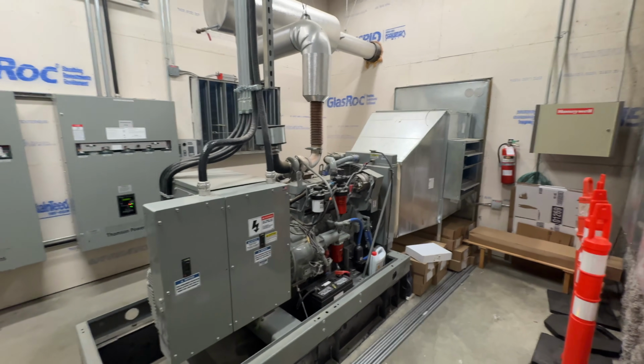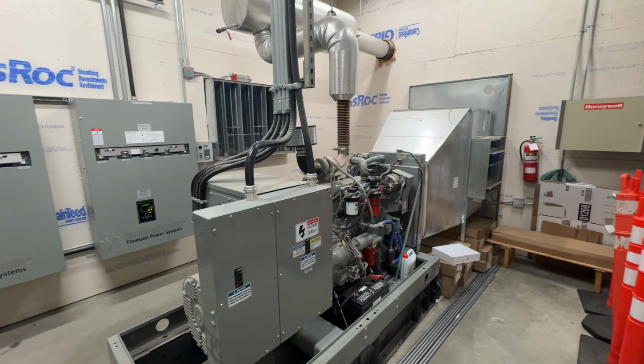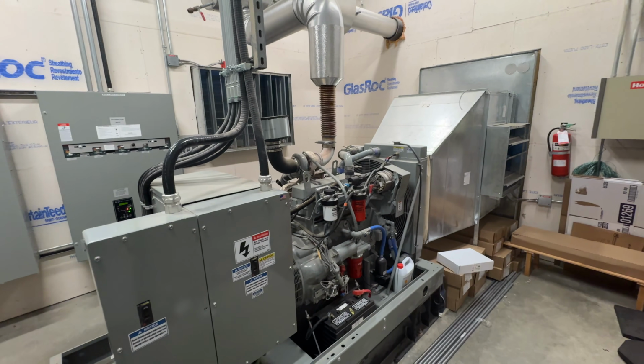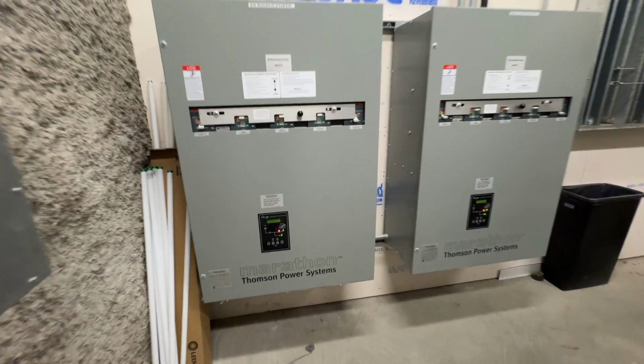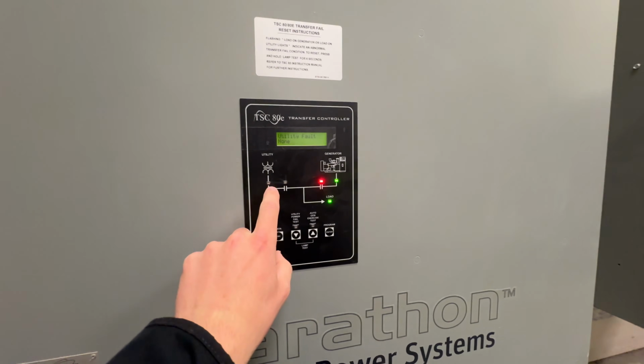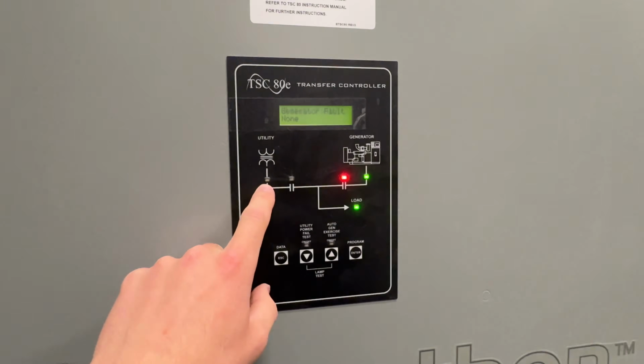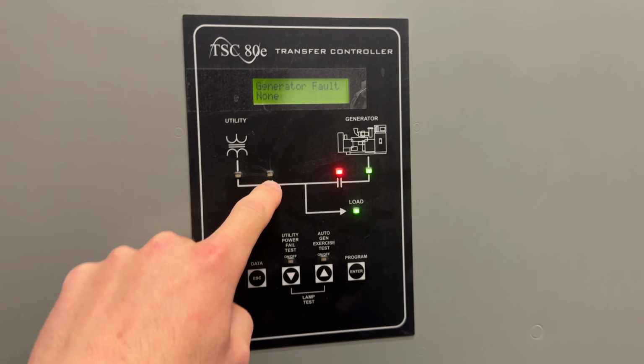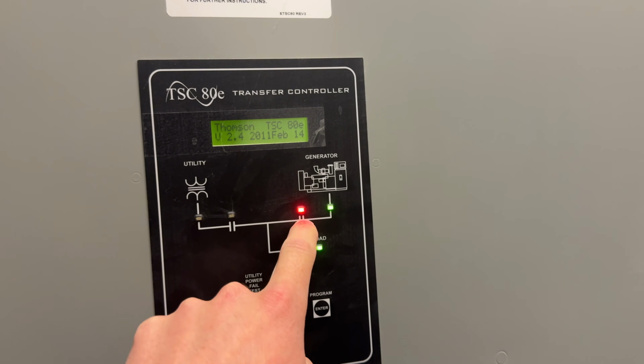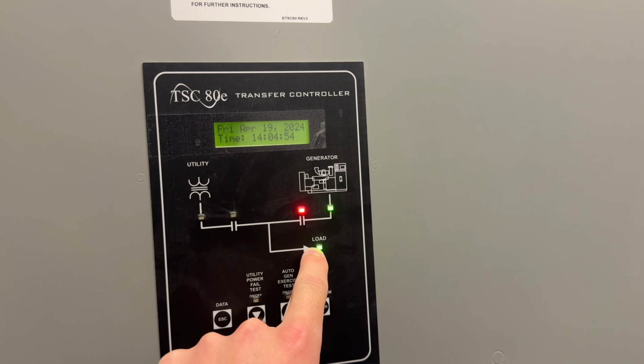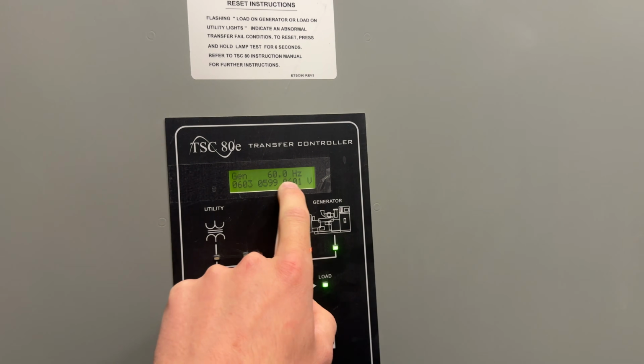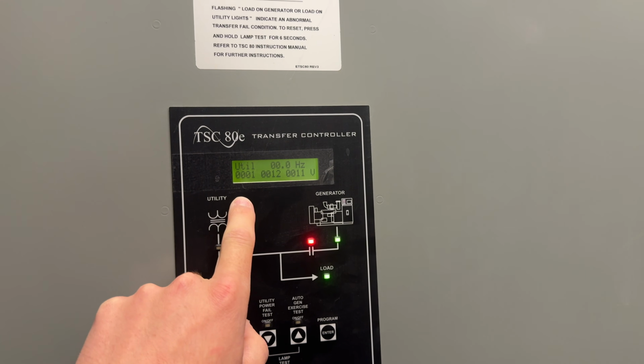Okay, so it's going to get a little bit hard to hear me. It is pretty noisy. Obviously, the generator is running. You can clearly hear that. And looking at the transfer switches, you are able to see that utility power is lost. Therefore, we are no longer closed in on that source. Generator power is on, and we are closed in on that power source going to our load. You can see 60.1 hertz. So we're putting out power and we're running on it.